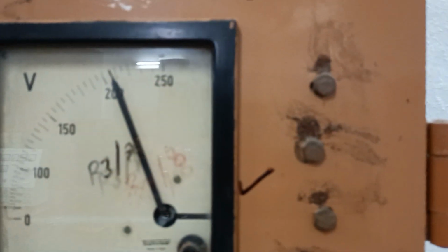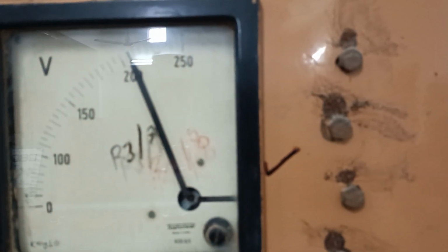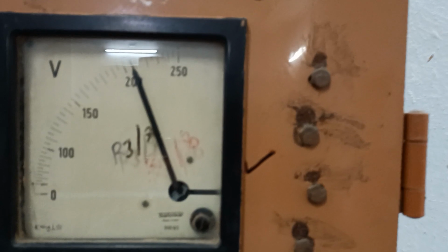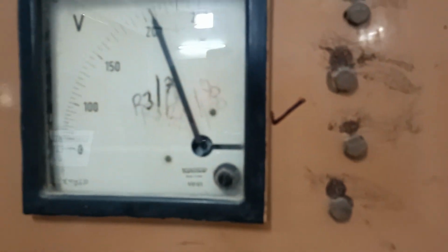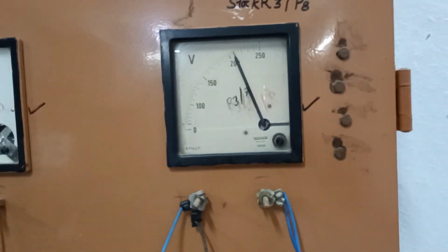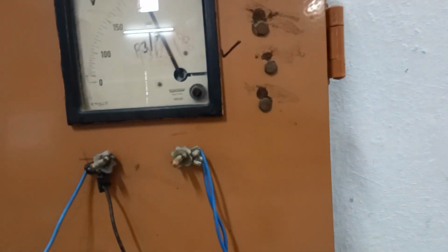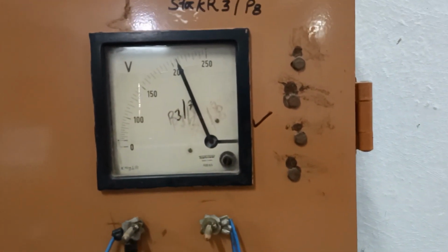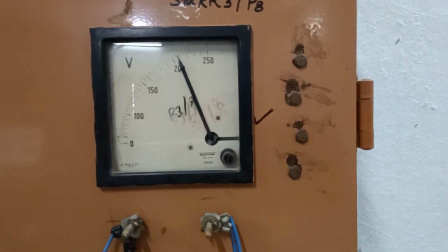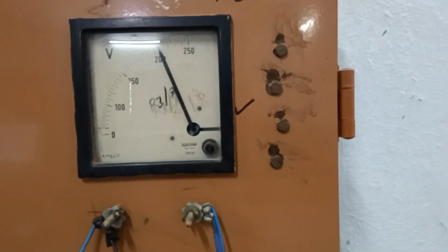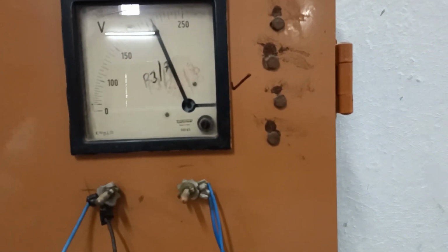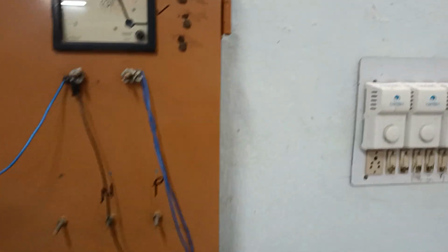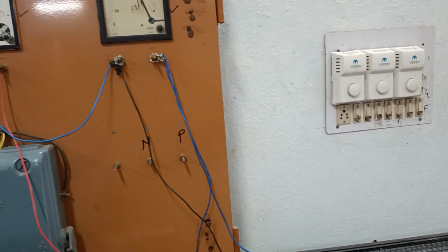Now I will measure the output voltage. You can see the output voltage is approximately 210 volt. So when it was under no load condition, the output voltage was 220 volt, but now under full load condition it is 210 volt. So this difference of 10 volt divided by the full load voltage, that is 210 volt, will give you the voltage regulation in percentage.